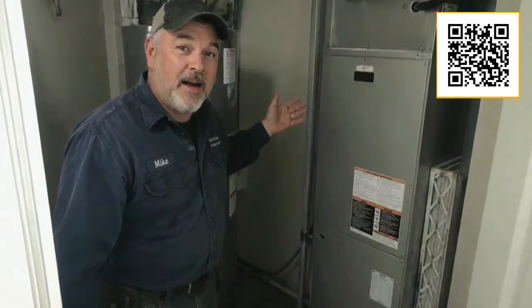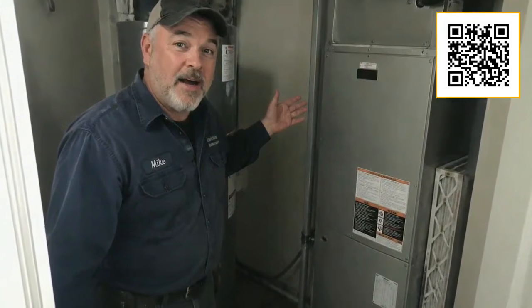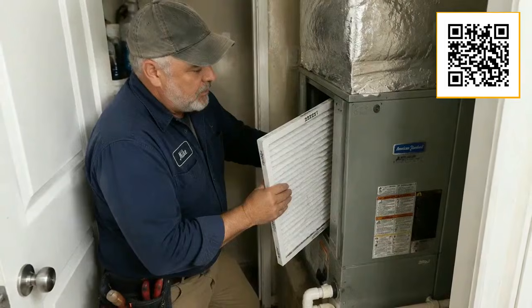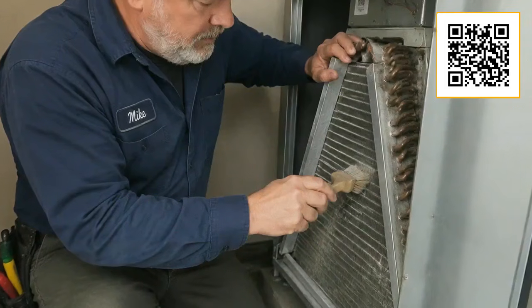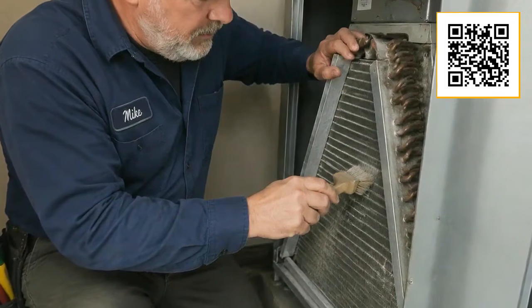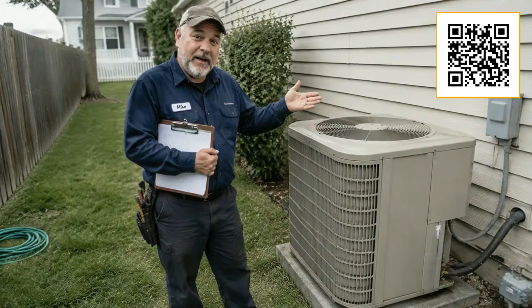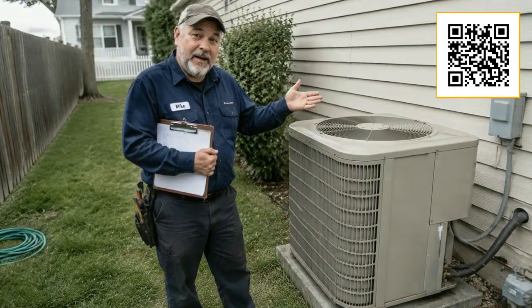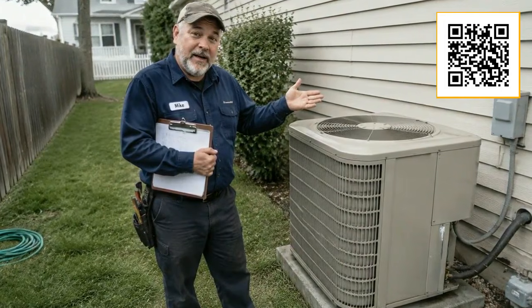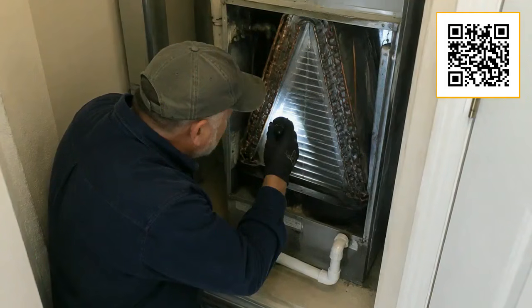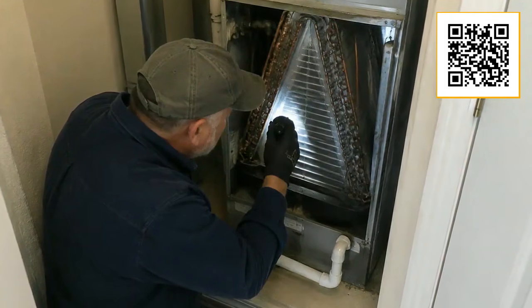The thing is, most homeowners never see the evaporator coil. It is tucked away in the air handler, and a basic filter change does not clean it. A good technician will check and clean it during a proper annual service. If your service visits only consist of someone glancing at the outdoor unit for 10 minutes, you are not getting a real inspection. I would encourage you to ask specifically whether the evaporator coil is being checked. That question alone tells a technician that you are paying attention.